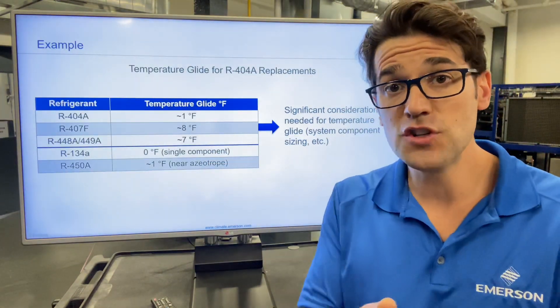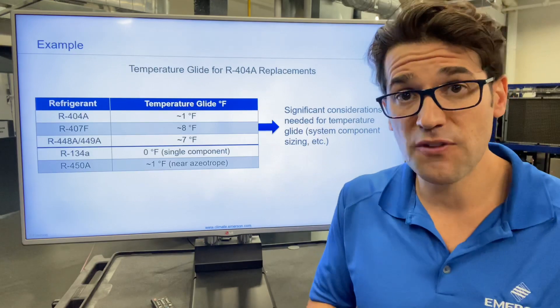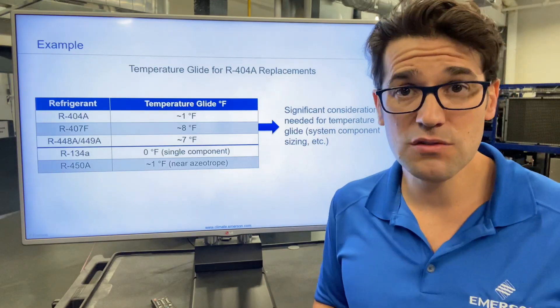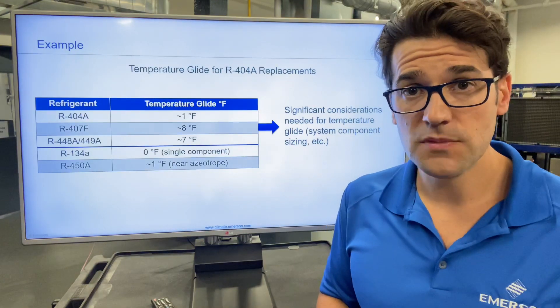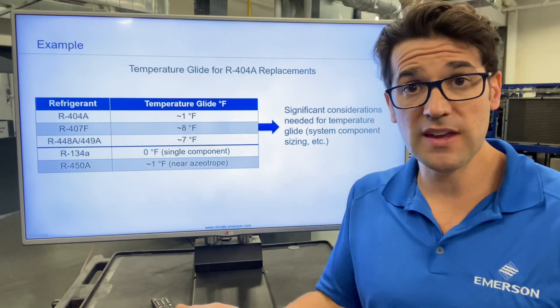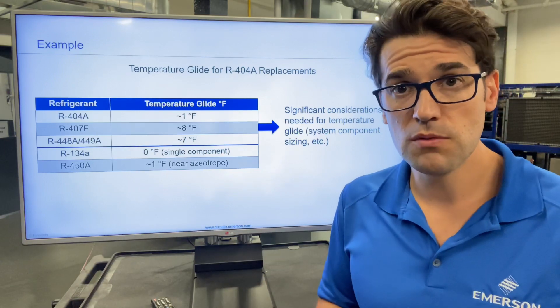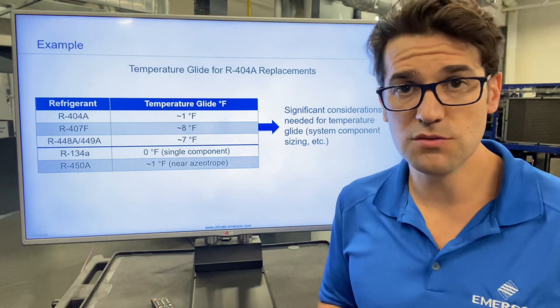For an example, if you're checking superheat on a medium temp system for eight degrees superheat and you use the bubble point, you may think you have eight degrees superheat, but you may actually have zero degrees superheat.